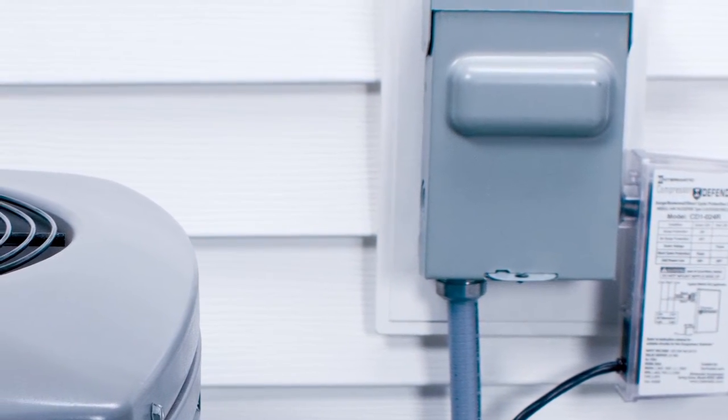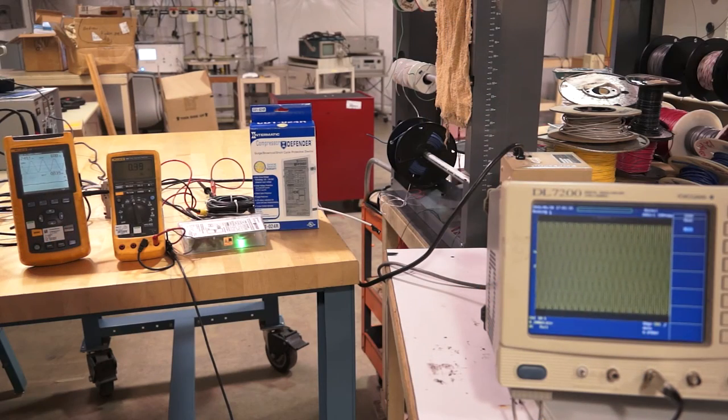The compressor defender will react to a power disruption or under voltage circumstance almost immediately. This demonstration will simulate a power disruption equaling three line cycles, which is just under one twentieth of a second on a 240 volt 60 hertz application.